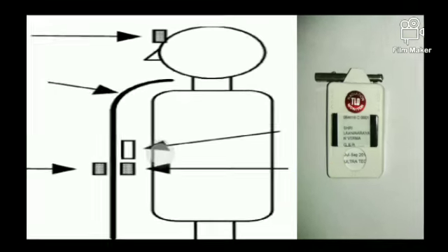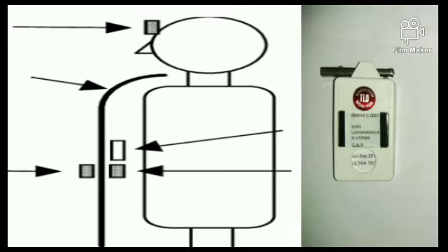Next thing is TLD badge, आप कहाँ कहाँ यूज़ करते हैं? We are using mainly in the head areas, in chest areas, in abdomen area, and wrist and in the fingers. So wrist, finger and head is mainly for nuclear medicine department and those who are working in the radioisotope areas.